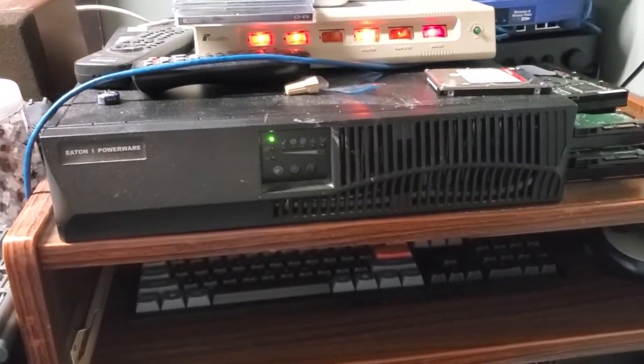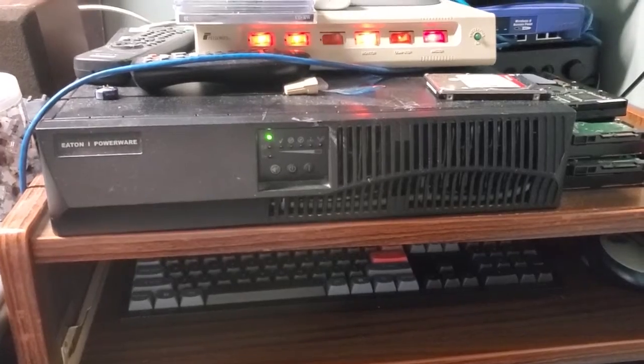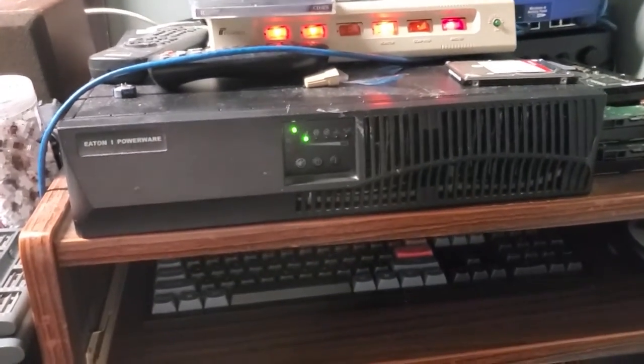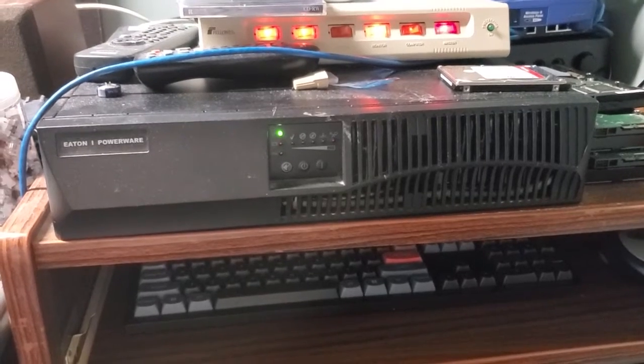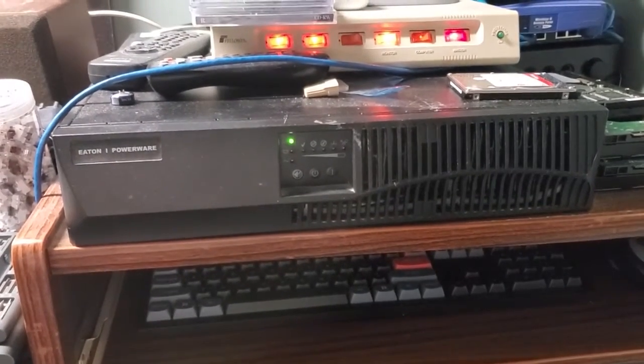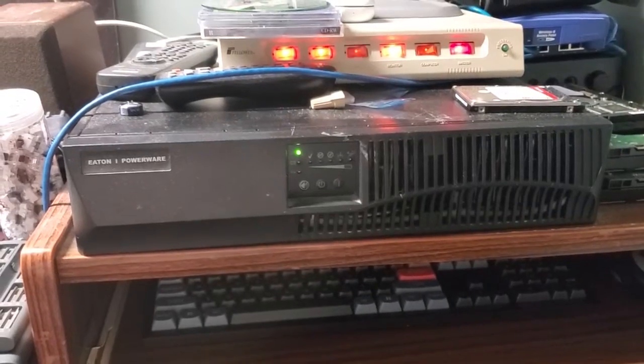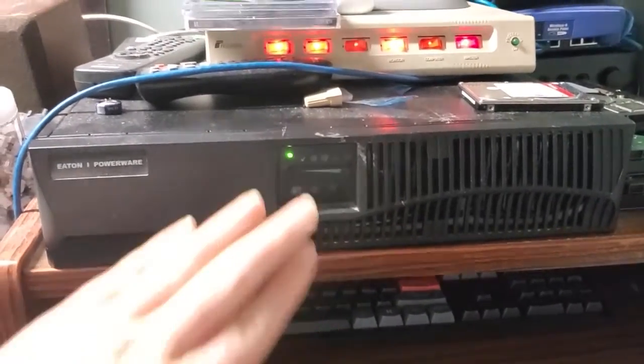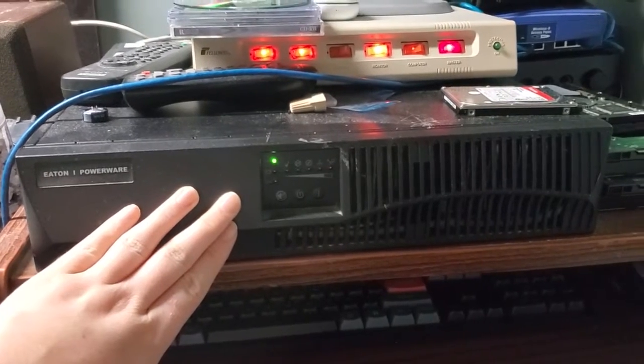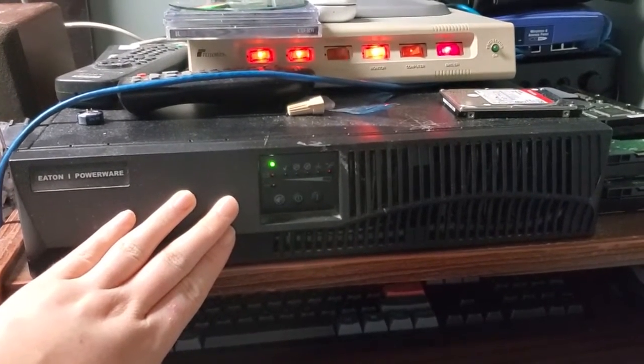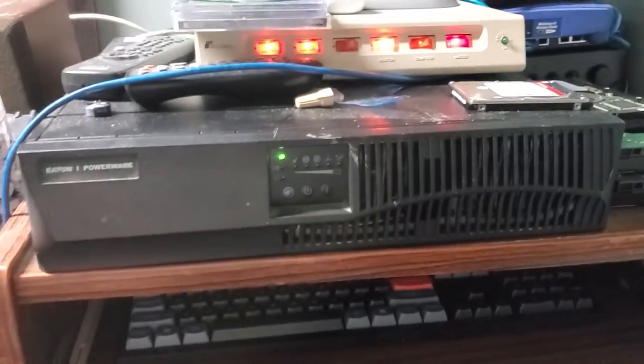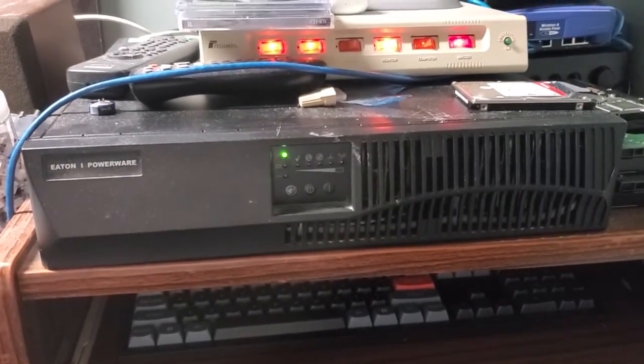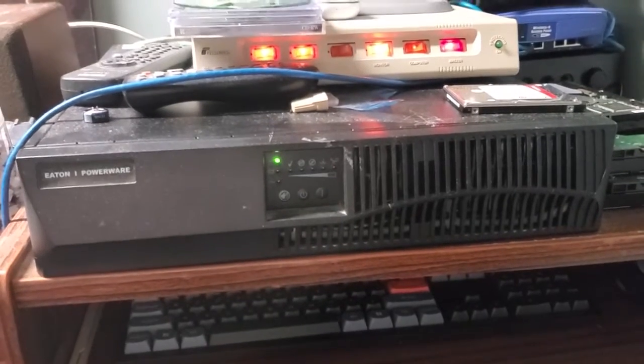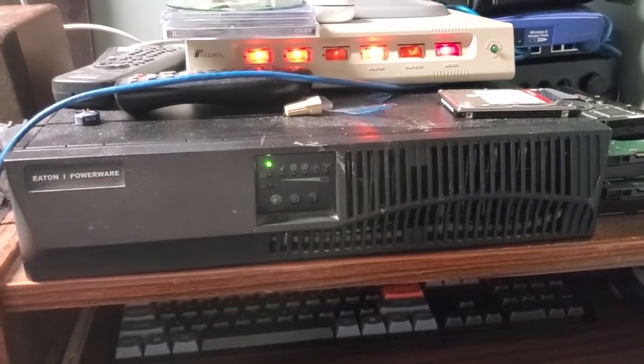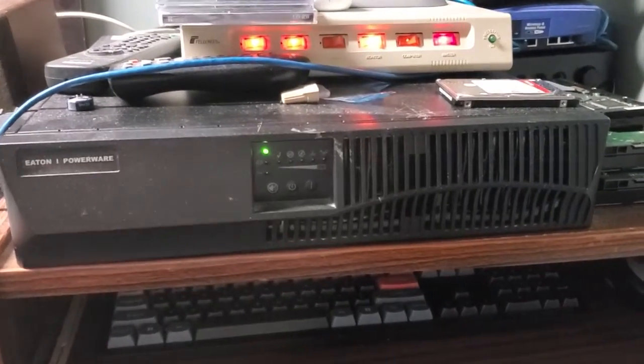Now very high-end UPSs, like this Eaton Powerware, which you'd find more in a commercial environment and not a home environment, are what's called a double conversion UPS, or sometimes an online UPS. That means this UPS is actually powering the load with its inverter all the time. Everything plugged into this right now is being powered not from mains power, but from its inverter, and all the mains power is doing is powering the inverter and charging the batteries.